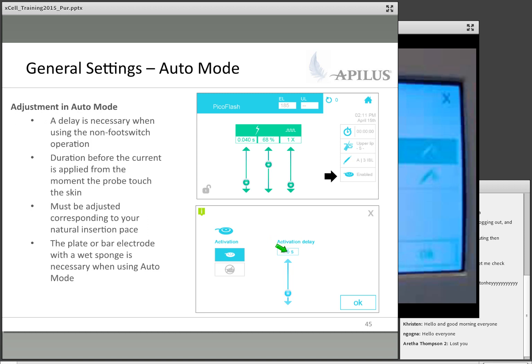How auto mode works is that you give the client the ground because you're going to have some sort of sensor. The client holds the ground. Remember, the ground has to be wrapped in that wet paper towel, the wet sponge, whatever you've got in order to have good connectivity. And then the probe will essentially sense moisture. When it touches the top of the skin, it senses the moisture on the skin, and it starts a countdown. This countdown is how long you have in order to do an insertion. And then the machine will automatically deliver the pulse, whatever you've got it set up to up here. So that activation delay is how long do you want from the time where my probe touches the skin to the time when the machine delivers the current.